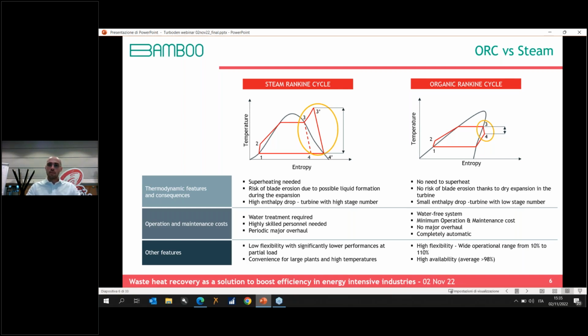So there is no risk of liquid droplet formation within the turbine. The expansion will always be dry, in design and off-design conditions, which simplifies the management of the system compared to typical steam turbines. This is one of the main advantages of organic Rankine cycle over steam: since the working fluid operates in a closed loop, we don't need any water on site to operate the cycle, which is interesting for applications where water supply can be problematic or expensive, like desert areas.